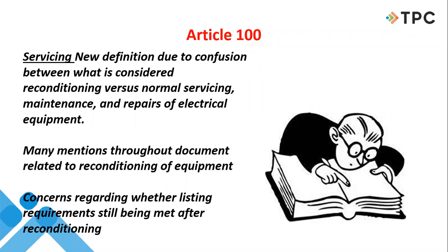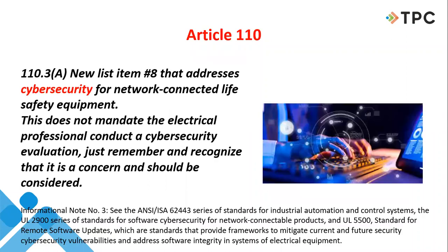Because there are conditions in the code where if you have rebuilt or reconditioned equipment, you have to provide labeling, you have to provide identification of what was done, when was it done, who did it, because technically, without getting into all of the other aspects of it, that's no longer a factory built piece of equipment whenever you tear something apart and clean it and spit polish it and make it look like brand new and then reassemble it again. It may be in exactly the same condition as it was when it arrived from the factory. It may even be in better shape. But the original manufacturer is no longer the person who built this particular piece of equipment. So they have to define the line: how much work can maintenance personnel or service personnel do to a piece of equipment with regards to repairs and replacements of parts and everything else before it's no longer considered servicing. It's now considered a rebuild or reconditioning.